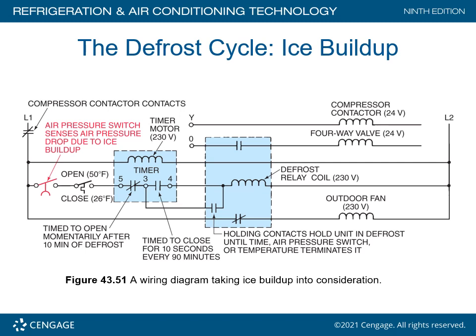Once again, we have the four-way valve. Notice that we're utilizing terminal O to energize. Here we have the defrost relay coil and outdoor fan motor. Holding contacts hold the unit in defrost until time, air pressure, or temperature terminates it. So once one device terminates, we go out of defrost and go back into the heating mode.